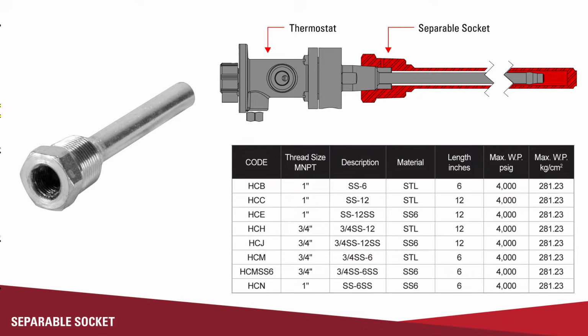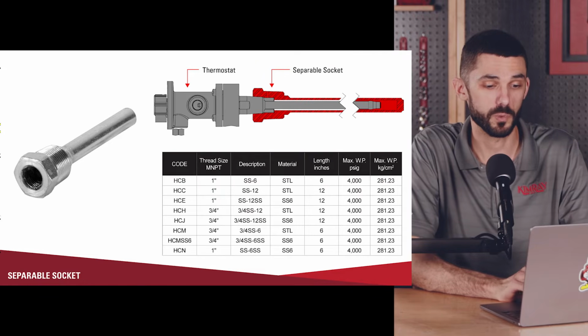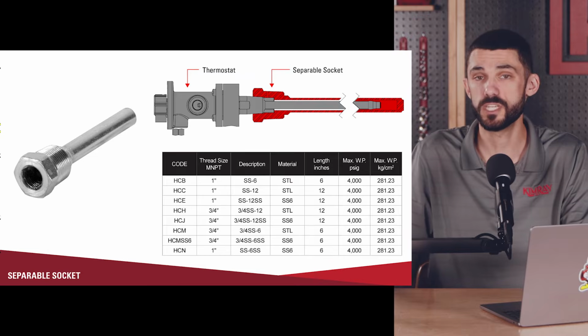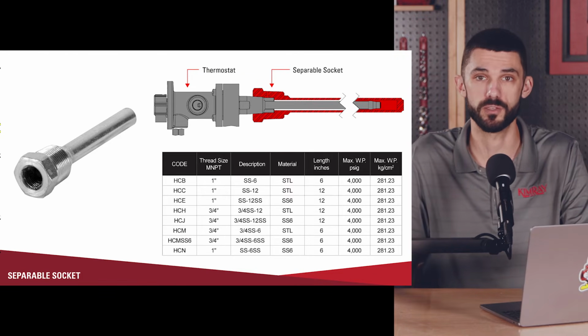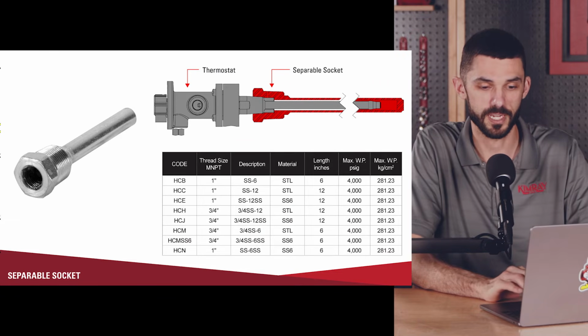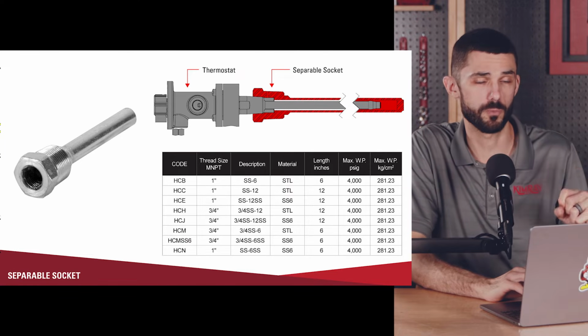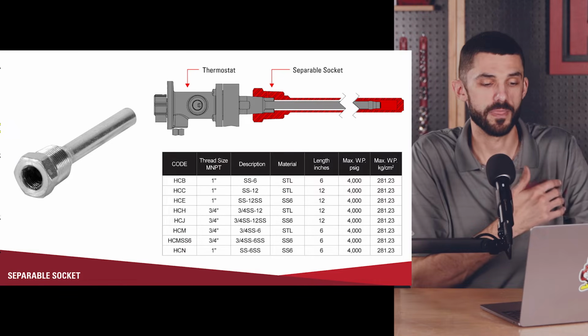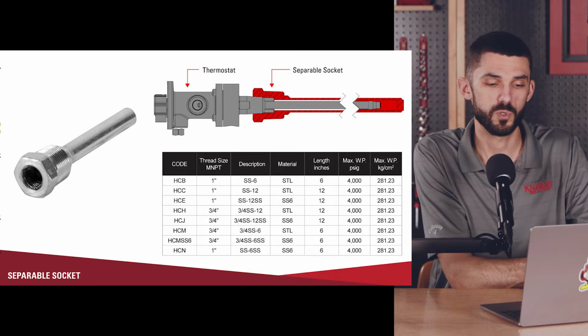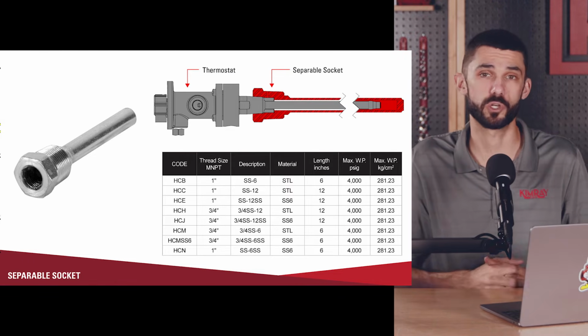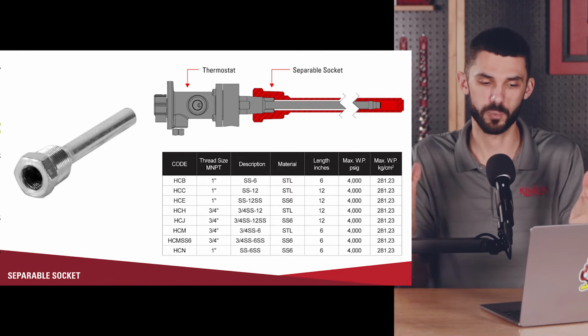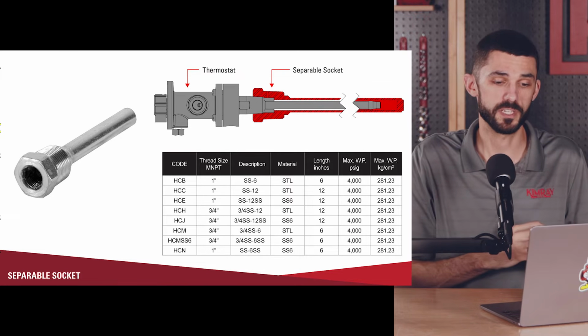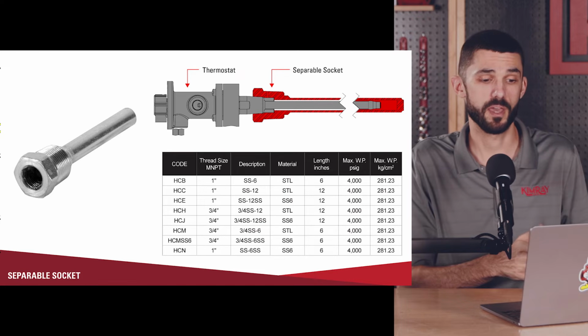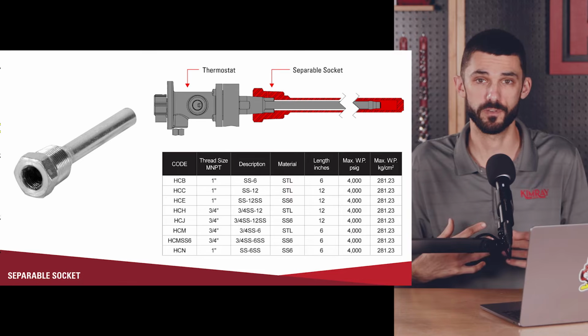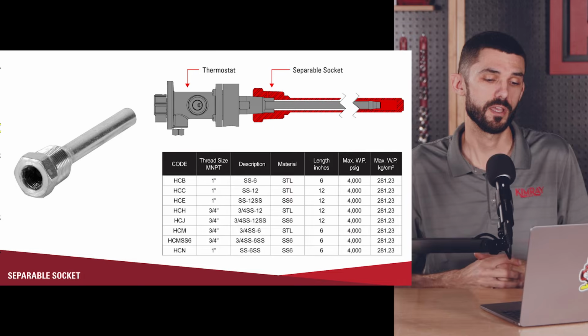With the use of the T12 as well as the high temperature shutdown manual reset pilots, you can use those with a separable socket. The reason why you would want to use this is that it allows you to remove the T12 from service without having to depressurize or blow down your vessel. It is a pressure containing device, and so you would install the Thermowell into your vessel first, and then the T12 can be installed into the Thermowell. You want to fill the Thermowell with some kind of high temperature grease, so that way the temperature of the process can be transmitted to the probe of the T12 efficiently. But with that, you can remove the T12 without having to depressurize your vessel. So it makes repair a lot easier and faster and more efficient.